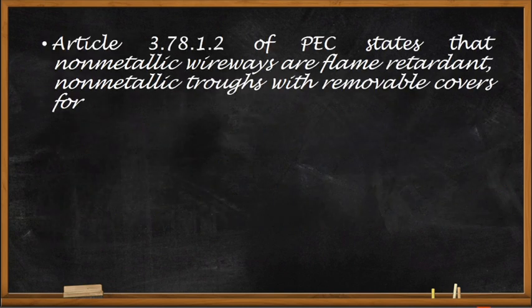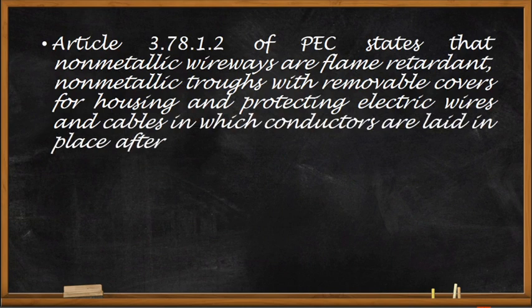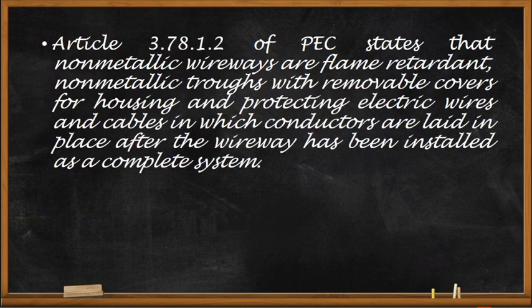Article 3.78.1.2 of the Philippine Electrical Code states that non-metallic wireways are flame-retardant non-metallic troughs with removable covers for housing and protecting electric wires and cables, in which conductors are laid in place after the wireway has been installed as a complete system. Being flame-retardant means the material will not allow flame to grow once heated.